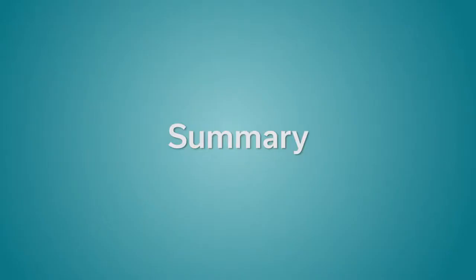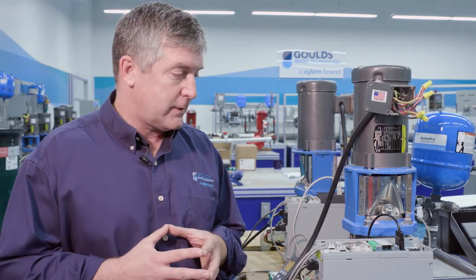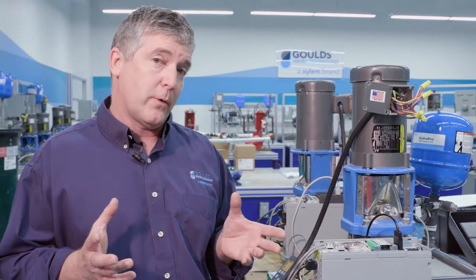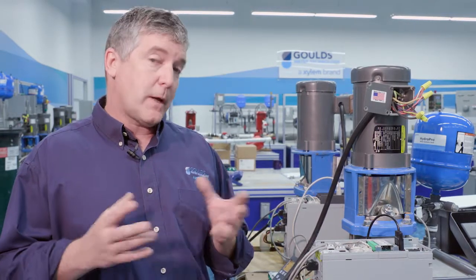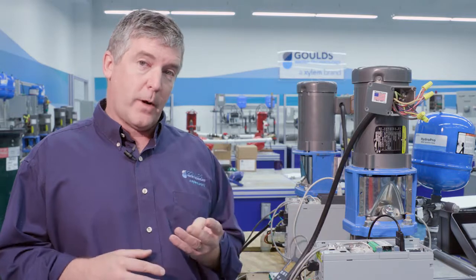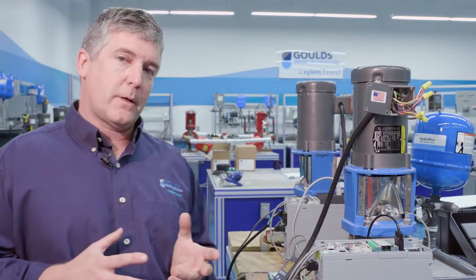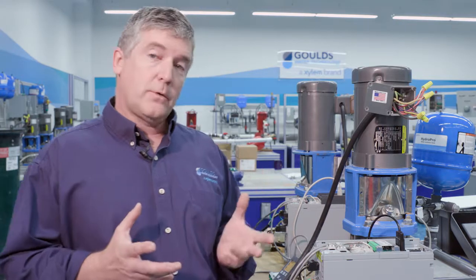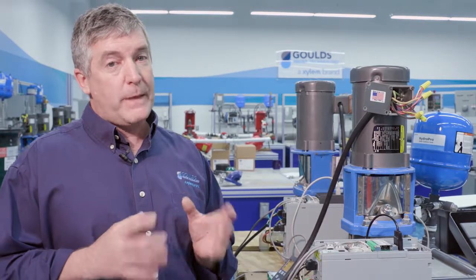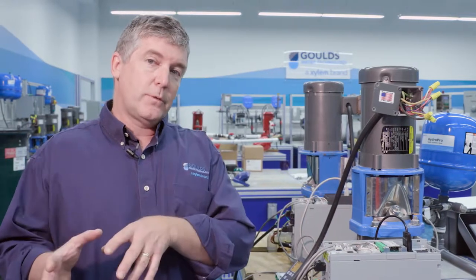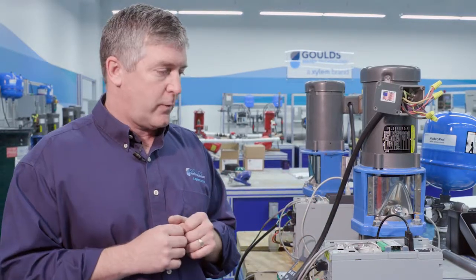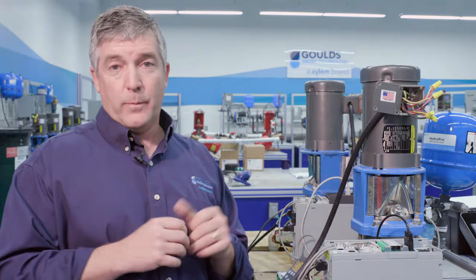So let's review some of the advantages of the IPC Advanced platform. We looked at several of those. One is wiring. So when you are operating a multi-pump, and keep in mind we can now go up to 4 pumps as opposed to 2 with the basic, all you got to do is connect 2 wires between each of the drives, and what we showed you was with the B card, which was terminal 5 to 5 in your other pumps and 7 to 7 in all of your other pumps. So just 2 wires as opposed to the harness that we were used to with the basic platform.